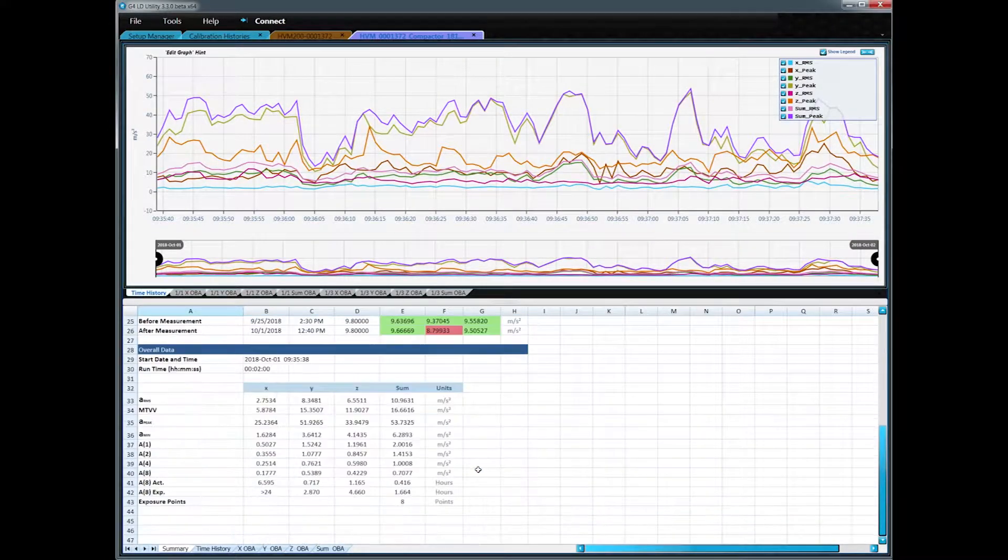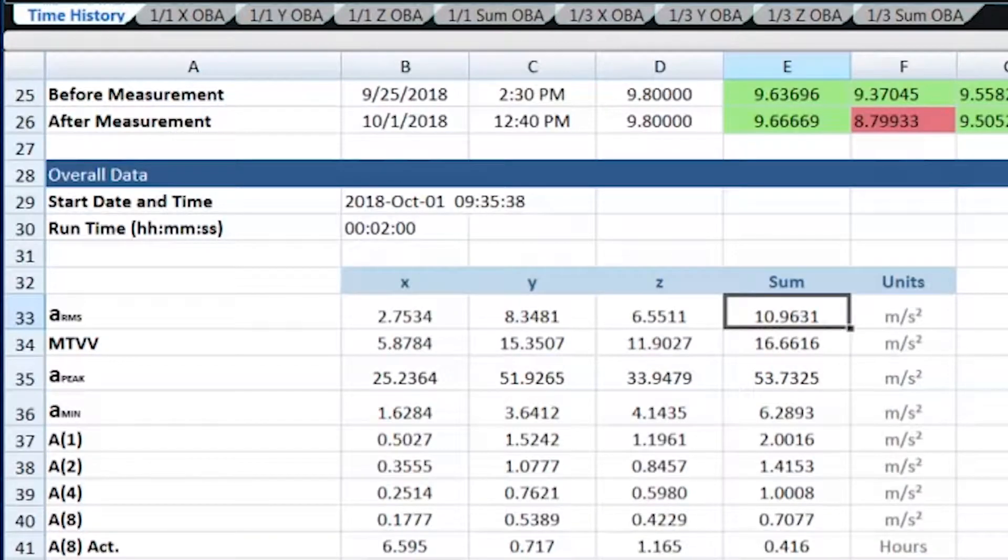We were told that the time on the compactor is around two hours per working day. So the ARMS level is 10.9631 meters per second squared. That is very high, but expected for this type of machine.